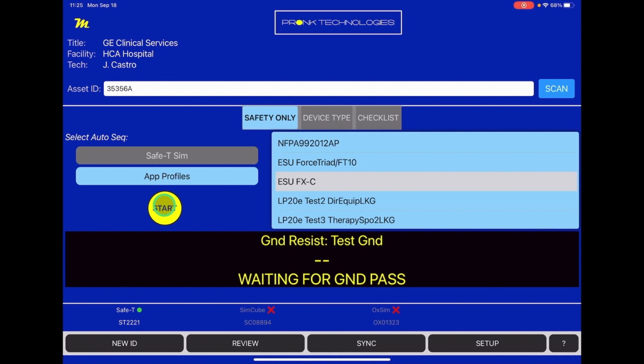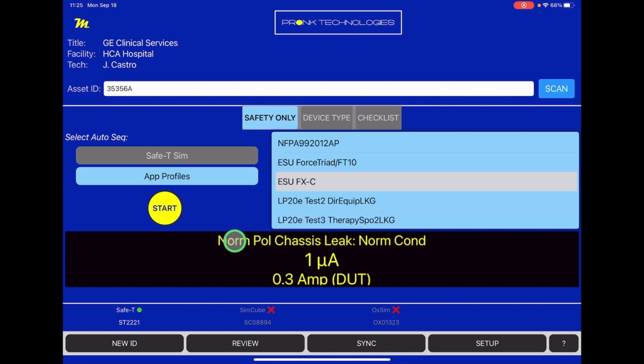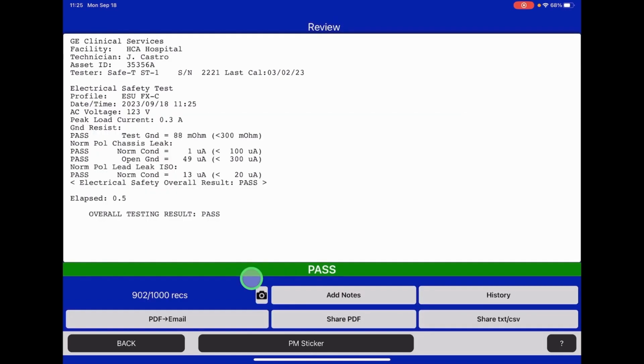So it's going to go ahead and start to do the test. And the first test it's going to run is the ground resistance test. And it automatically told the analyzer to do that test. It's running it, and it's going to save that result and go on and perform only the test we programmed it to do for this FXC device. And you can see here we're running through a chassis leakage test with the open ground. In the center here you have your measured values. Below that is the current draw that the device is drawing during this testing.